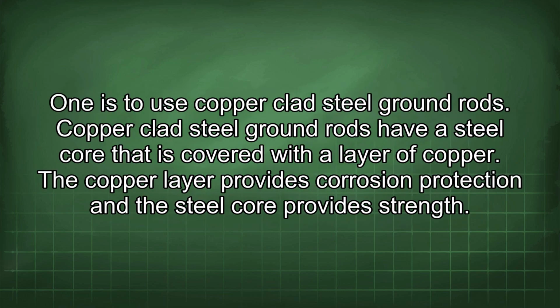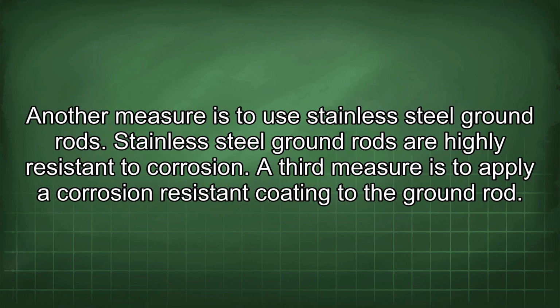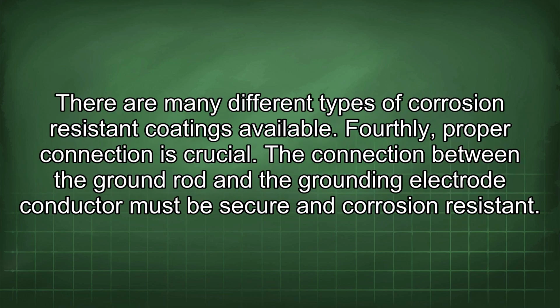One is to use copper-clad steel ground rods. Copper-clad steel ground rods have a steel core that is covered with a layer of copper. The copper layer provides corrosion protection and the steel core provides strength. Another measure is to use stainless steel ground rods. Stainless steel ground rods are highly resistant to corrosion. A third measure is to apply a corrosion-resistant coating to the ground rod. There are many different types of corrosion-resistant coatings available.